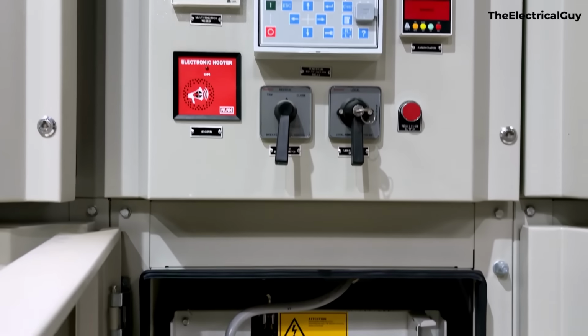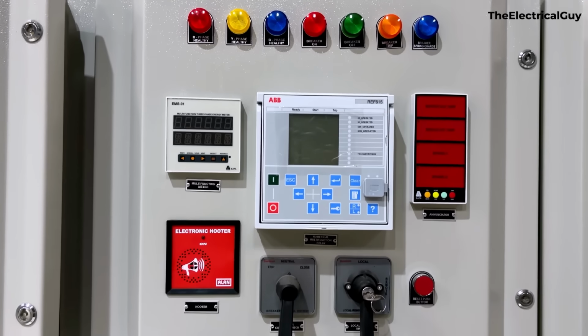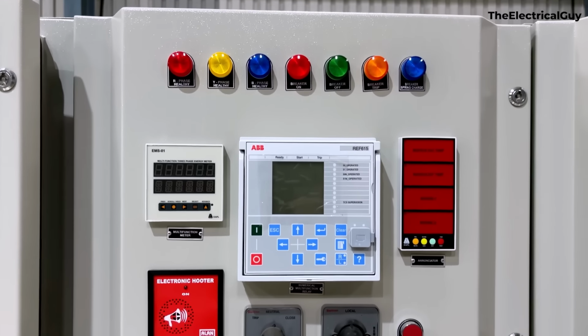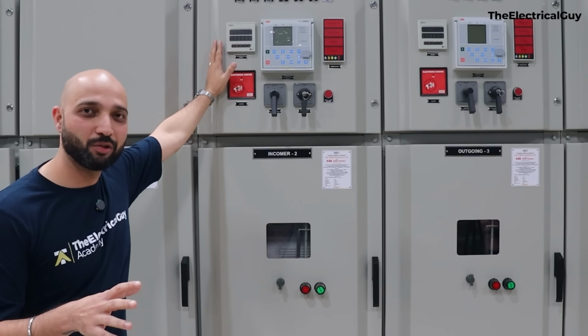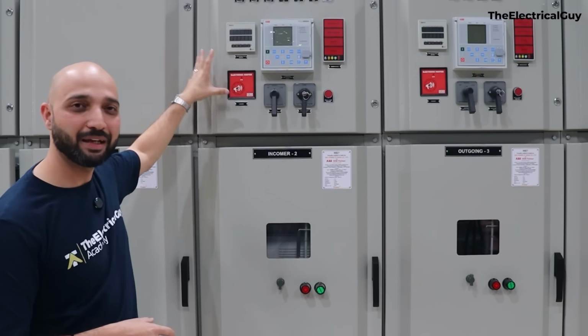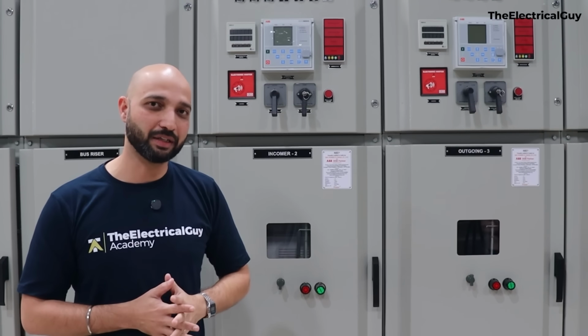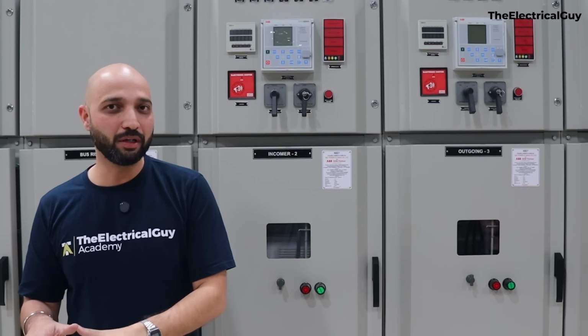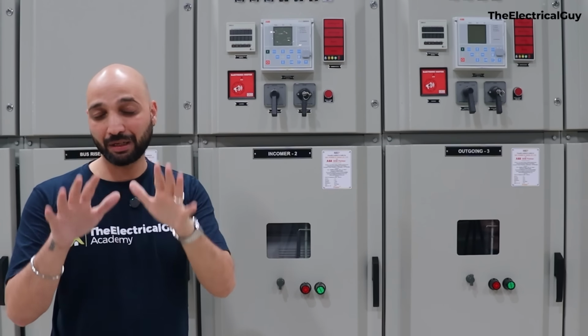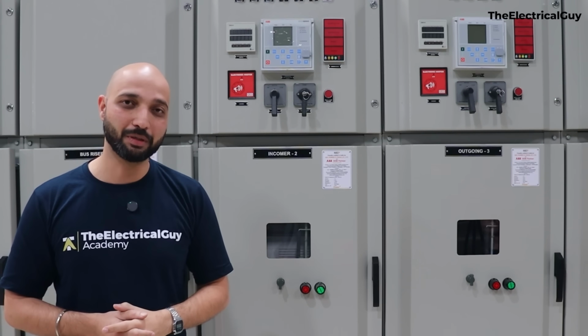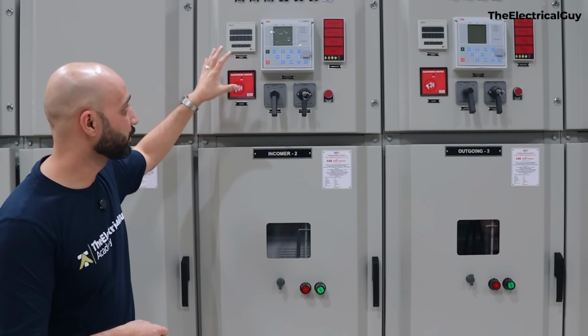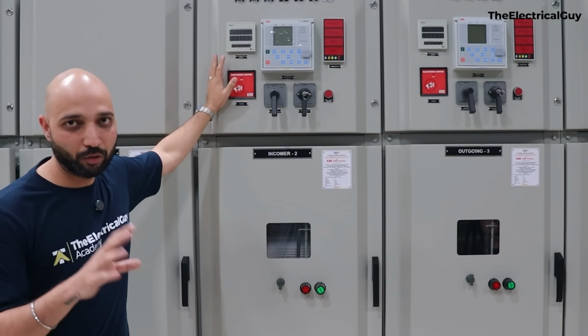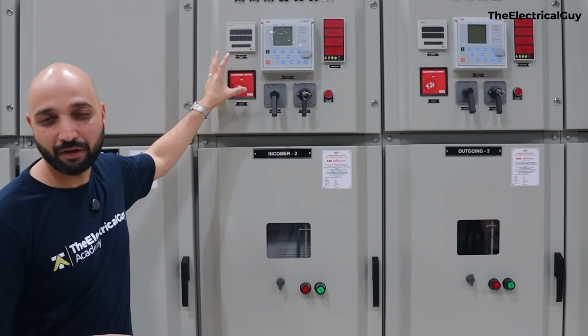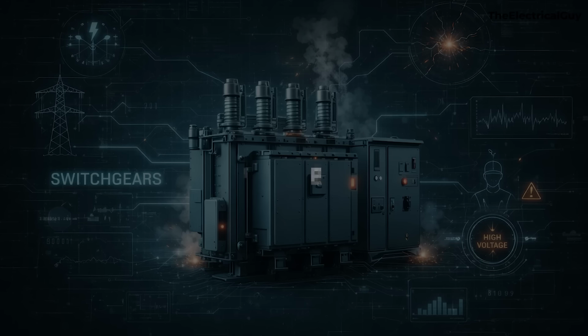The middle portion is the circuit breaker chamber, and then we enter into the third chamber, which is the low voltage chamber. Now why is this low voltage? Because we are not handling any 11 kV or 12 kV inside it. We will always have 110 volt DC or 220 volt DC, which is much lower compared to what our system is giving us. So that's why this is called a low voltage panel. Now let me quickly show you what all the things are that we have on this low voltage side.